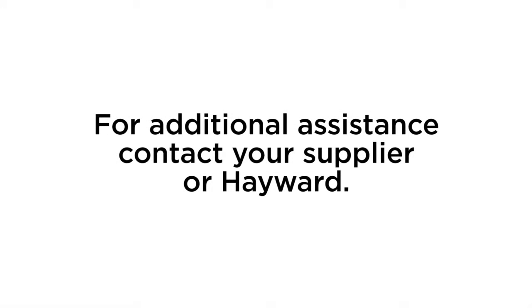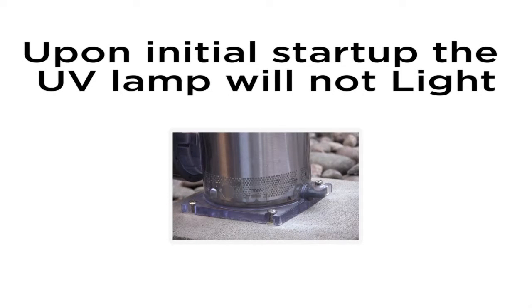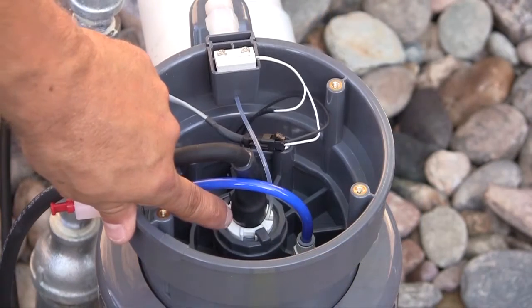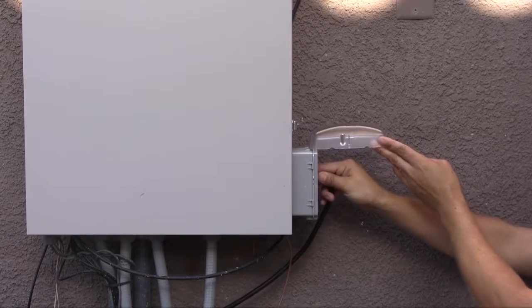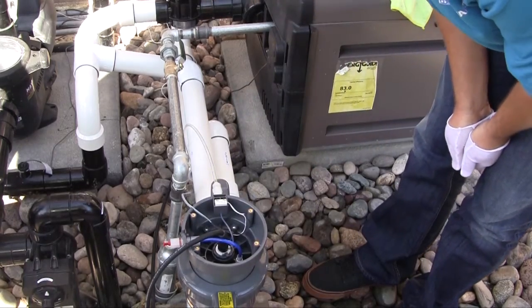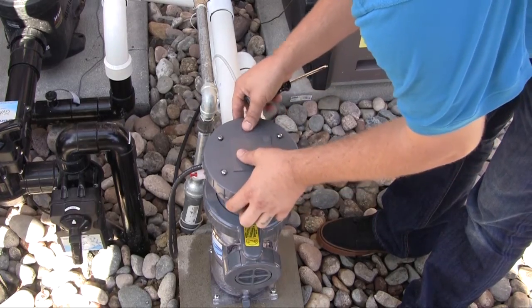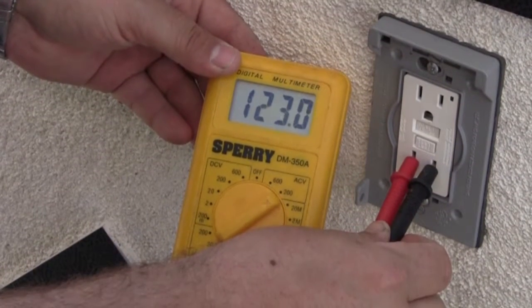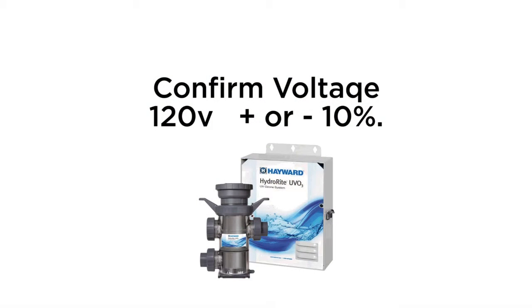Troubleshooting. The following information will help guide you through any problems you may have at time of initial installation or during operation. For additional assistance, contact your supplier or Hayward. Upon initial startup, if the UV lamp will not light, the following could be the problem. Determine whether the flow over temperature interlock LED is lit and resolve the issue as covered during the operation part of this video. The lamp may have become disconnected from the 4-pin connector. Disconnect the power cord from the electrical outlet, open the vessel cap and confirm the lamp connector is firmly in place. Check all exposed wires for a possible loose connection. Plug the electrical cord back into the electrical outlet only after the electrical enclosure cover has been reinstalled. Verify that the power cord is plugged into a properly functioning electrical outlet. Test the electrical outlet and make sure the GFCI has not tripped. You should confirm the availability of the same voltage as indicated on the electrical label on your HydroRite unit: 120 volts plus or minus 10%.